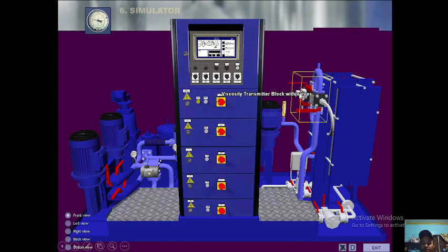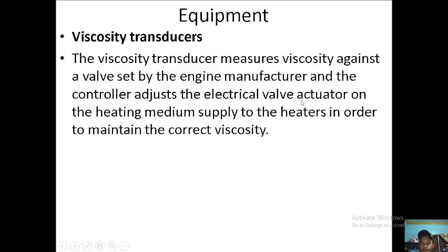Okay, next we have the viscosity transmitter or the viscometer here, or Viscotherm. The viscosity transducer measures viscosity against a value set by the engine manufacturer, and the controller adjusts the electrical valve actuator on the heating medium supplied to the heaters in order to maintain the correct viscosity.